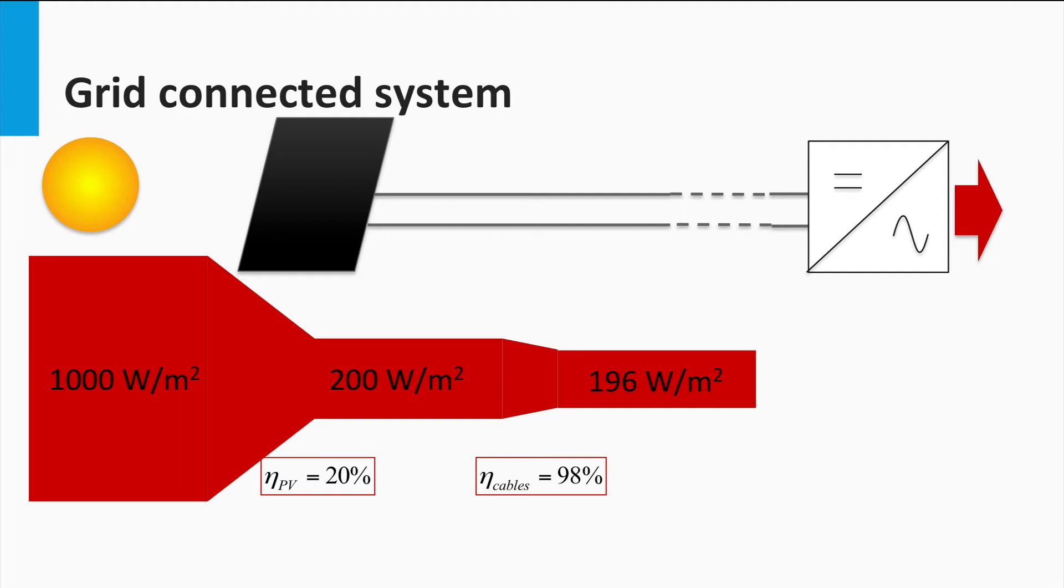usually the efficiency of the inverter is dependent on the power at which it operates. It is seen from practice that the inverters typically reach the rated efficiencies at around 50% of the rated operating power. For the sake of simplicity, we shall assume an average efficiency of 95% for the inverter.